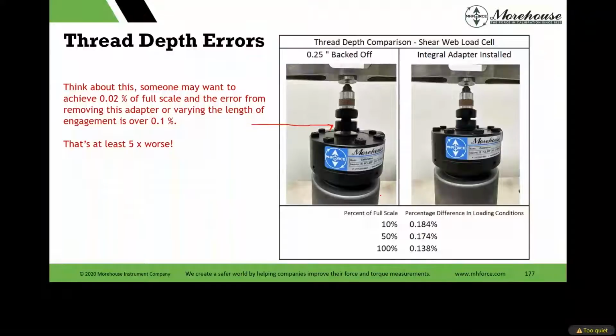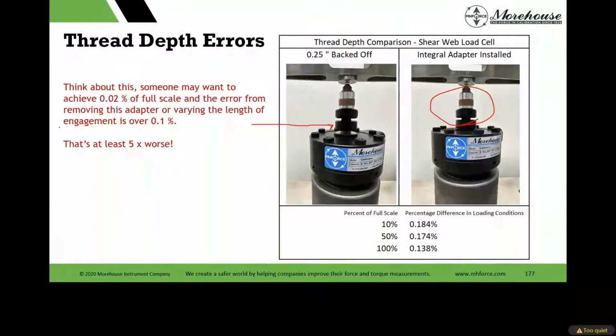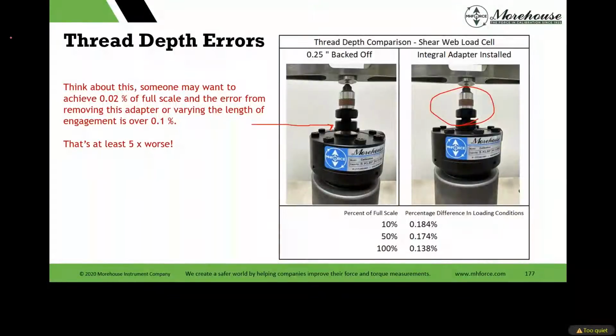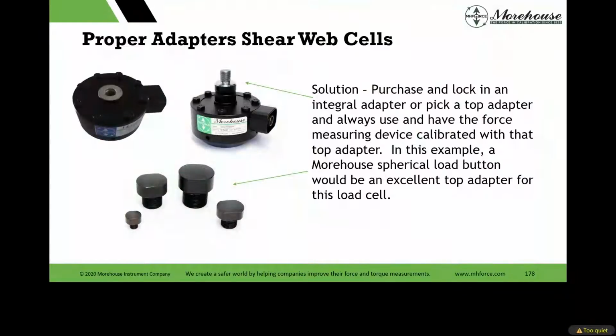If you take it out and put it back in, we get very, very close. So also reproducibility, these adapters here, reproducibility of the load cell gets so much better. When I do a 2.5-day course, we play with these, take them out, do all kinds of different things. So solutions here, this is bad. This piece here, we see a lot of these cells come into our lab. I would like within the next 5 years to not see any of those come in and see people start implementing policies to say, okay, I'm going to send you my adapters so you can thread it exactly the same amount that I do. However, if you send in a compression adapter and it's tension and compression, tension has the same exact error. So it's just so much better to lock an adapter and do away with this.